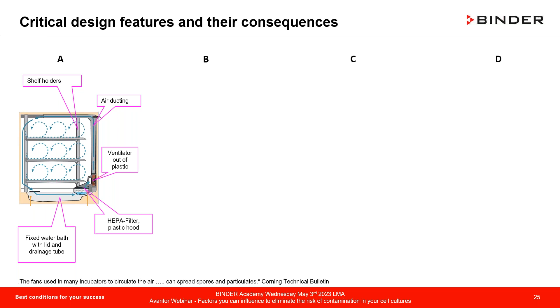You have a HEPA filter right now, which is a collector. Any filter, regardless if it's a HEPA filter or a coffee filter at home in the coffee machine, is a collector. In this case, type A collects contaminants right in the vicinity of CO2, of cell cultures, and I don't feel very comfortable with that. Especially since these have to be exchanged at the latest every 6 months, and when you remove them, you're spreading that. You have a full, filthy HEPA filter, and that's not good for containing contamination.